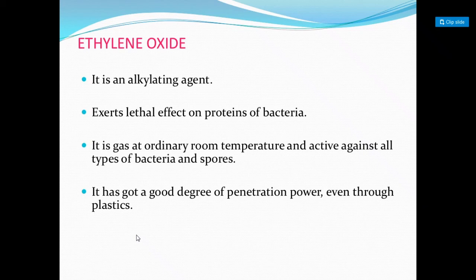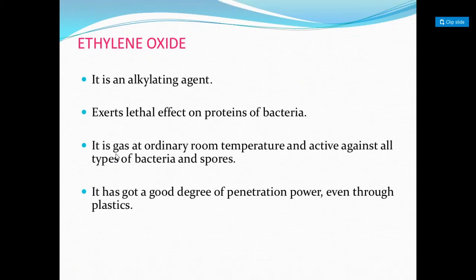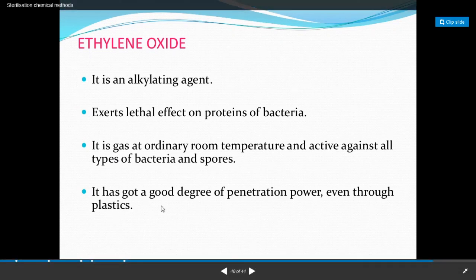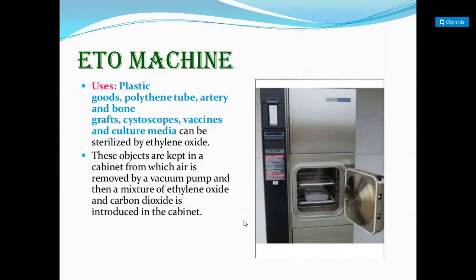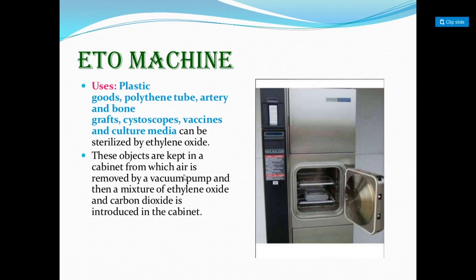Ethylene oxide is a gaseous sterilizing agent and an alkylating agent that exerts lethal effects on proteins of bacteria. It is a gas at ordinary room temperature and is active against all types of bacteria and spores, with good penetrating power even through plastics. Uses include sterilization of plastic goods, polythene tubes, artery and bone grafts, cystoscopes, vaccines, and culture media. Objects are kept in a cabinet from which air is removed by a vacuum pump, then a mixture of ethylene oxide and carbon dioxide is introduced.